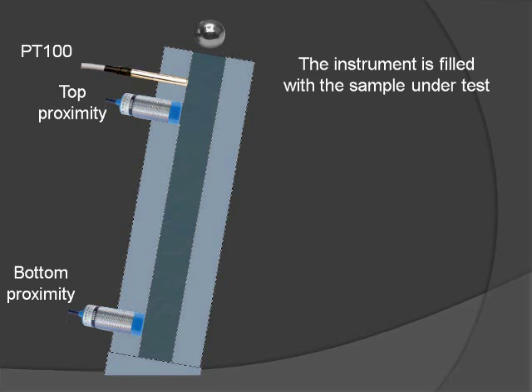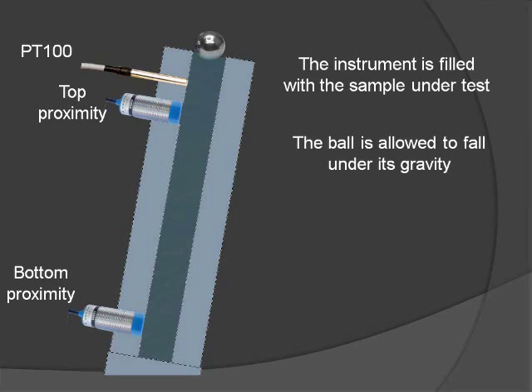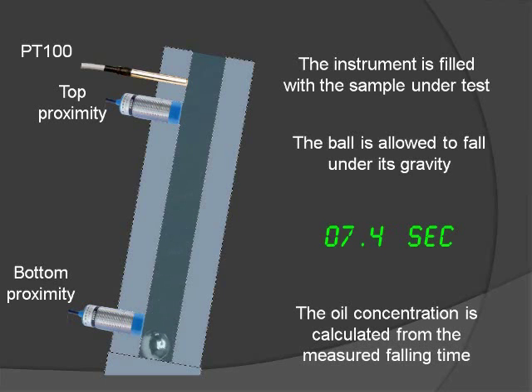At the beginning of the measure of oil concentration, the instrument is filled with the sample under test. Then, the ball is allowed to fall under its gravity inside the instrument and roll on its surface. When the ball exits from the top proximity sensor active area, the counter is activated. When the ball enters the bottom proximity sensor active area, the counter is deactivated. The measured falling time is used to estimate the sample oil concentration.